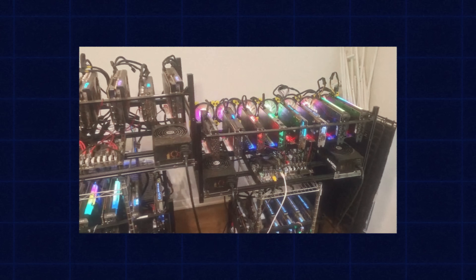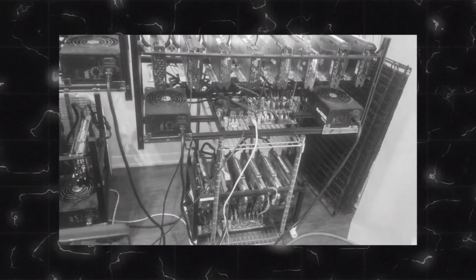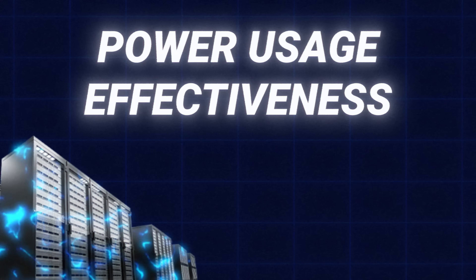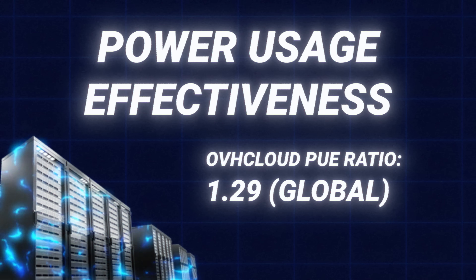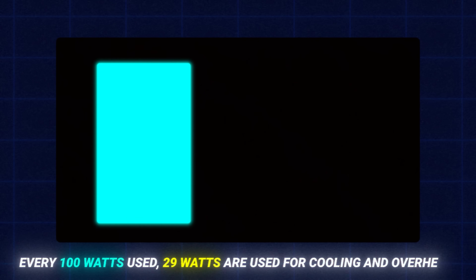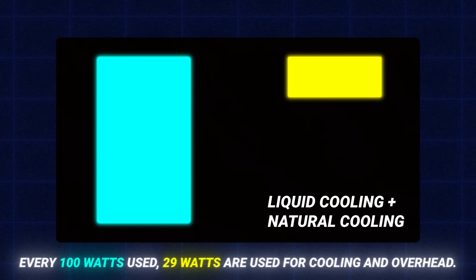Data centers use a metric called power usage effectiveness, or PUE, to determine the effectiveness of the energy being used. OVH Cloud's PUE was 1.29, which means for every 100 watts of power used, 29 watts goes to controlling overhead like power and cooling devices. Using things like the liquid cooling systems mentioned before would significantly bring that number down.